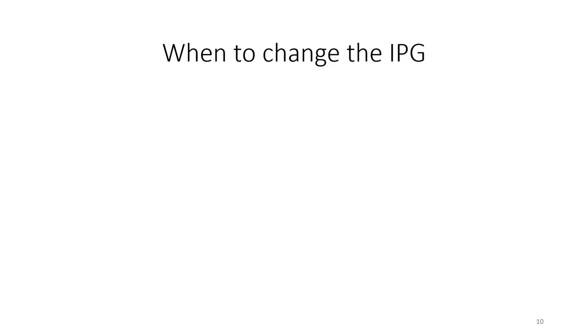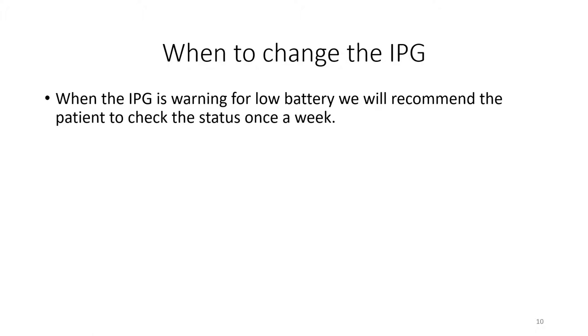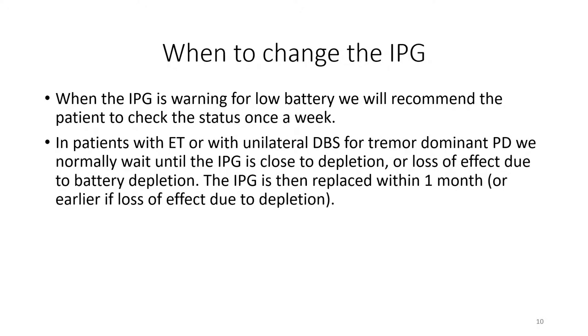An IPG may be changed for other reasons, such as increasing the programming options, but most often it is replaced when the battery is close to depletion. When the IPG is warning for low battery, we will recommend the patient to check the status once a week. In patients with essential tremor or with unilateral DBS for tremor dominant Parkinson's disease, we normally wait until the IPG is close to depletion or loss of effect due to battery depletion. The IPG is then replaced within 1 month, or earlier if there is loss of effect due to depletion.